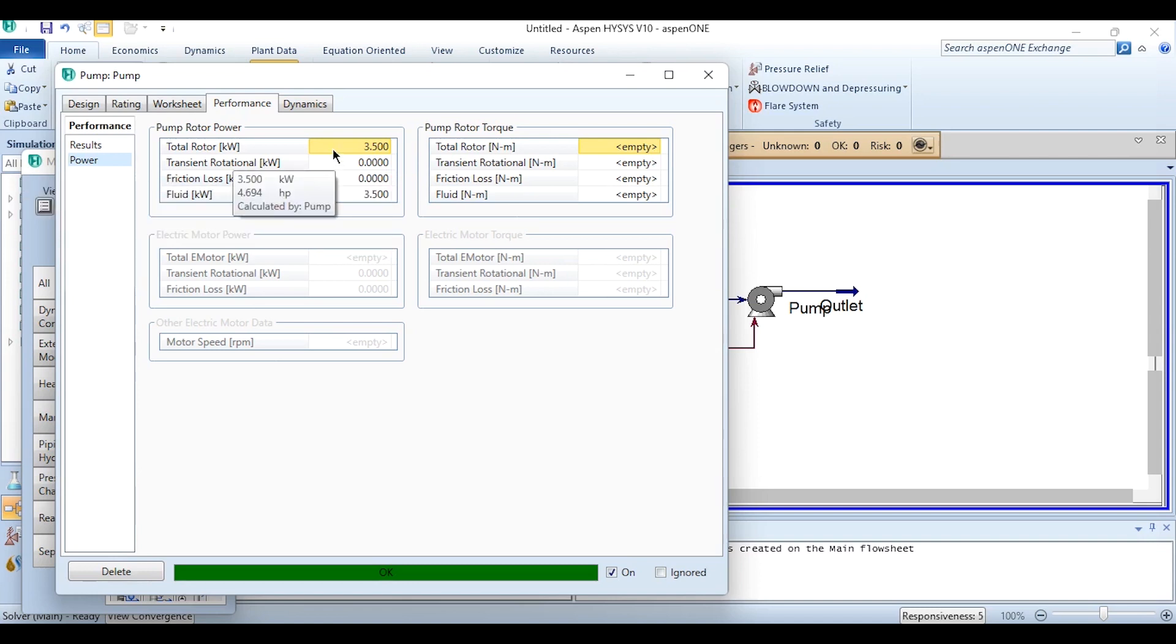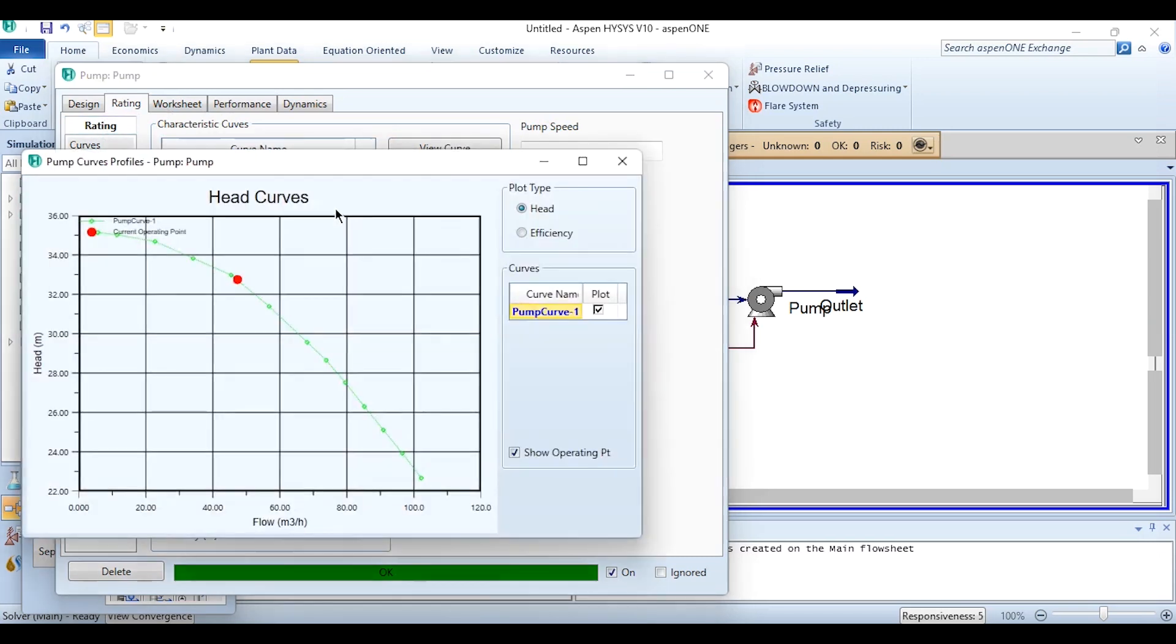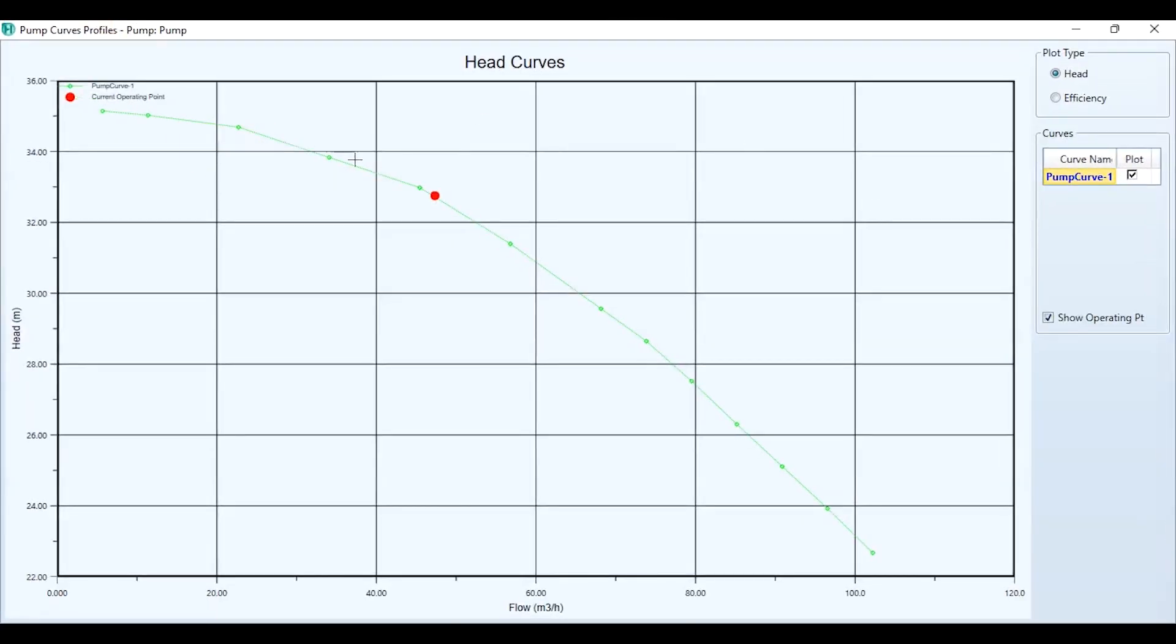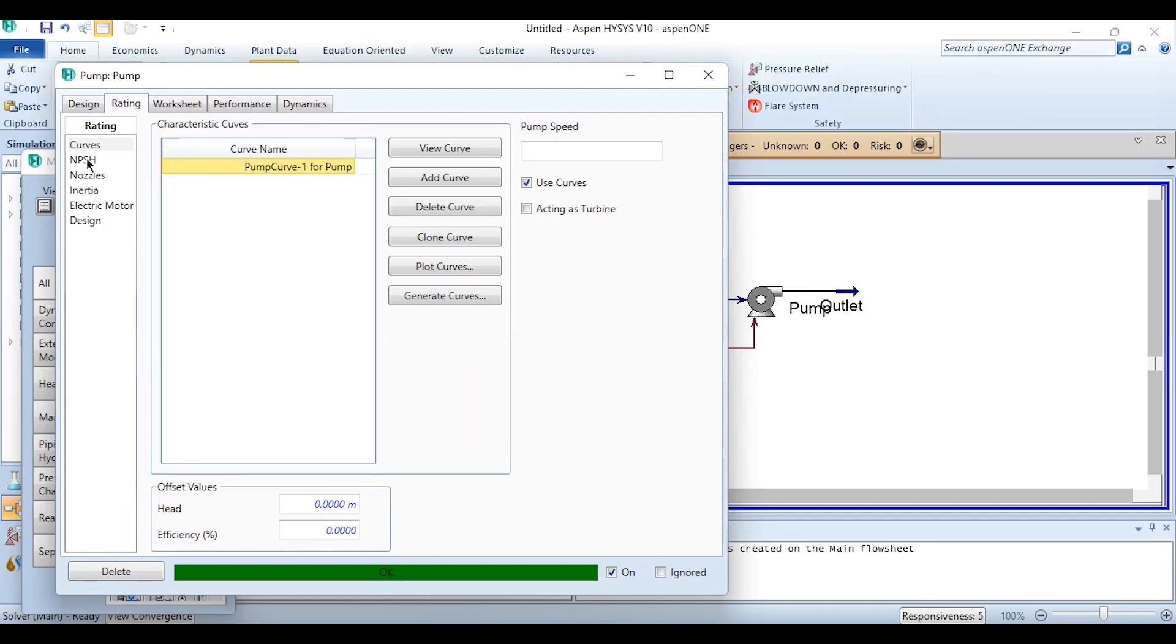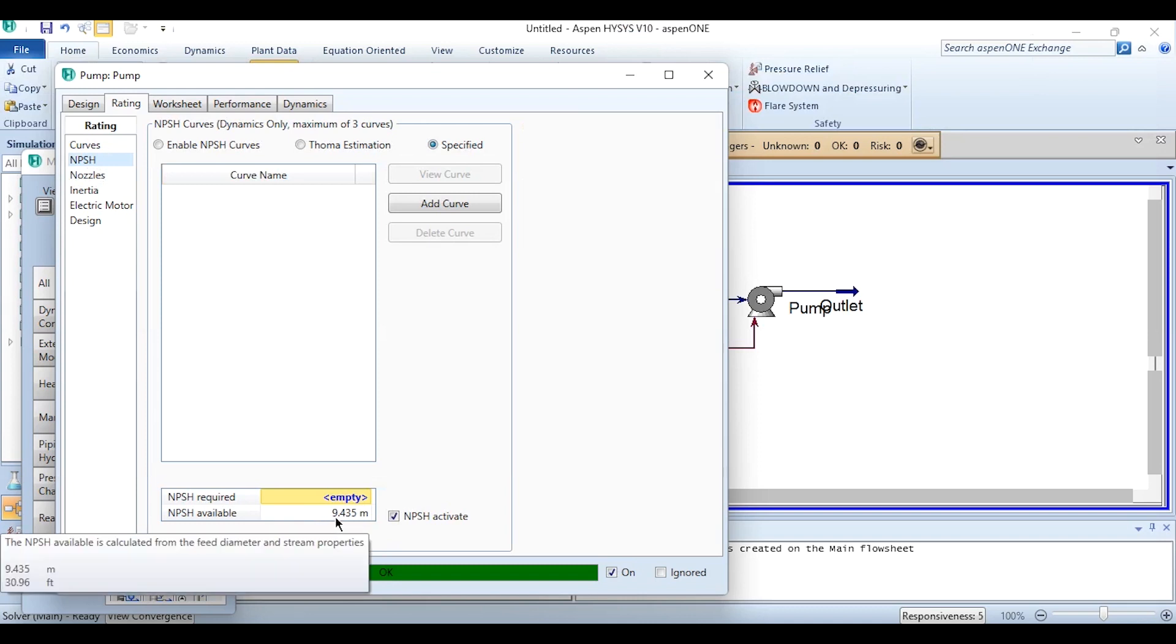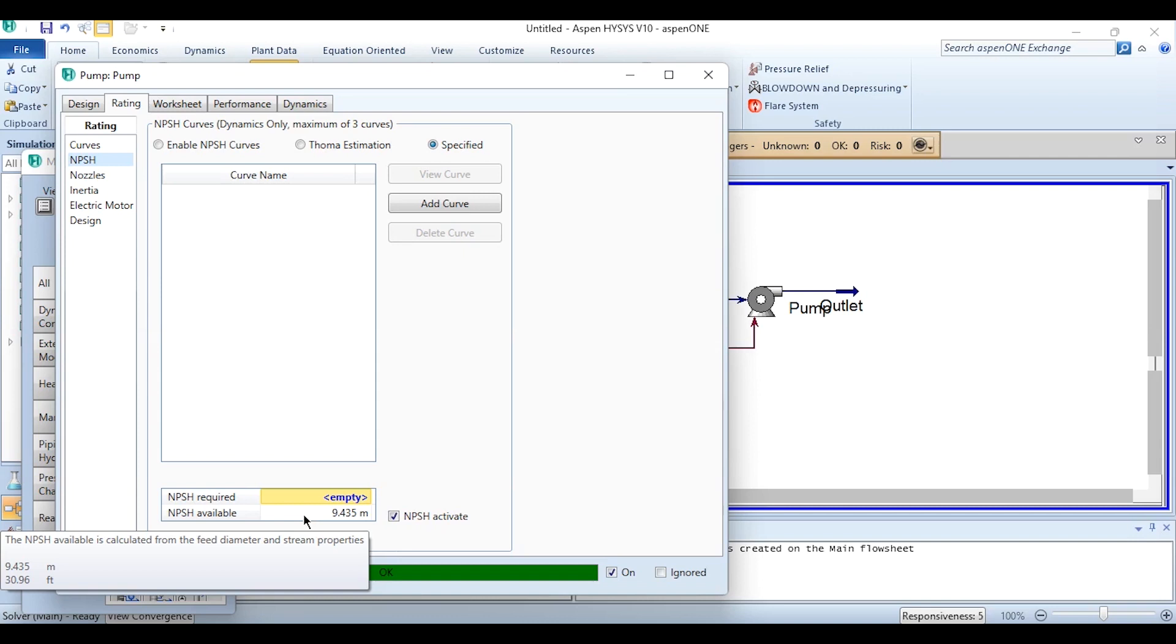If you go to this Power Result, total rotor power is this. There is no loss considered, frictional loss. The fluid power is 3.5, but actually once we consider the frictional loss this fluid power will be 3.5 but the total rotor power will increase in the system. Now if we go back to this Rating tab, if you want to plot the curve, you can see that the curve and the red point shows the operating point of the curve. And this is by head, like flow versus head. And if you change it to efficiency, that's flow versus efficiency. You can see the red point is again in the curve, so it shows that the data is right as well.